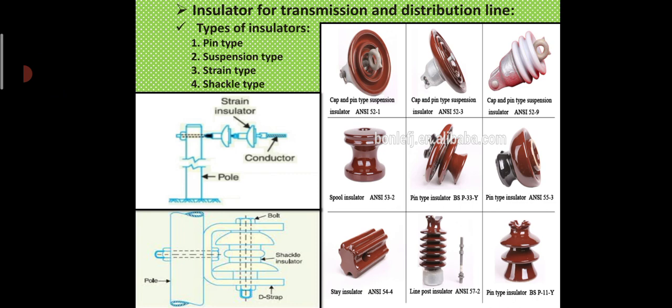While in suspension type insulators, there are different discs and, depending upon the system voltage, the required number of discs are used and a string is prepared. When any disc is punctured or damaged, only that disc has to be replaced and the whole string is not required to be replaced. Two discs of cemented cap type suspension insulators are shown. To increase the length of the leakage path, grooves are provided. Due to this, the inner side of the disc remains dry even during the rain.